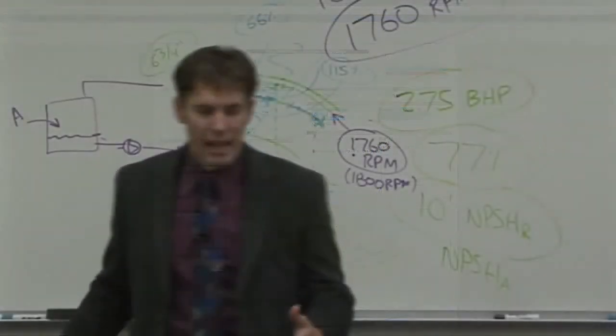And then it gives us our minimum flow rate. Minimum flow rate is very important when we get into systems that are operating with two-way control valves. And we actually talk about that in other classes. So there's a lot of valuable information that we're given here. And because we use 40% propylene glycol, we go over to the fluid, and it gives us our specific gravity and our viscosity. Information that's important as we plot some of this pump information. So hopefully that helps you understand how to select a pump.